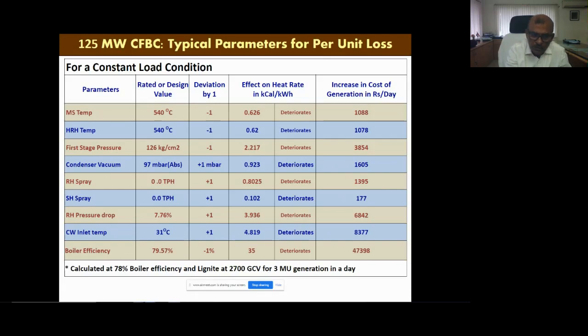Similarly, we have HRH, and this also shows in the first stage pressure; 1 kg gives around 3800. I'm talking about the third one: condenser vacuum 97. If you have a 1 millibar drop, the heat rate increases by 0.923, and the increase in cost is 1605. Then there are the superheater spray, reheater spray, and CW inlet temperature. It is 31 degrees; if it increases by 1 degree, the heat rate increases by 4.819. These are all based on analysis and evaluation.